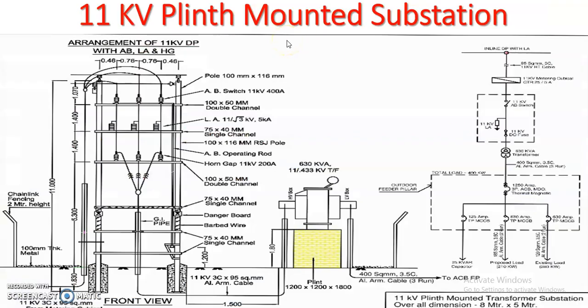So this is our 11 kV Plinth Mounted Substation. The first figure indicates the layout of the Plinth Mounted Substation and the second figure shows the single line diagram of Plinth Mounted Substations. In this figure you will see first is the AB switch. 11 kV supply is connected to the HV winding through this AB switch, lightning arrestor, that is then horn gap or DO switch. It is directly connected to the HT terminal or HV terminal of this transformer.